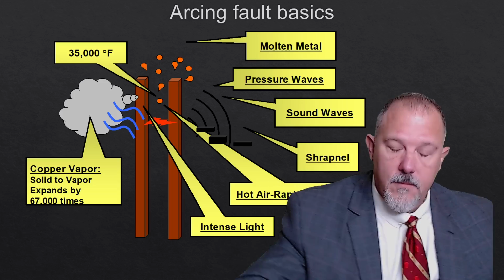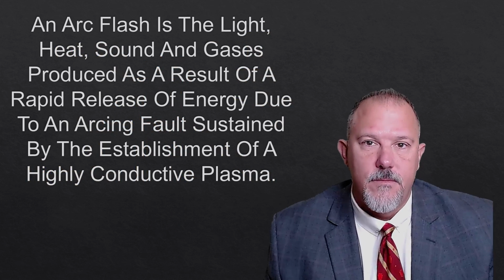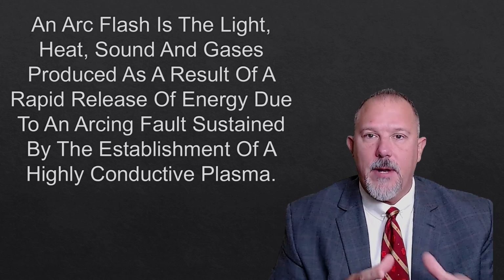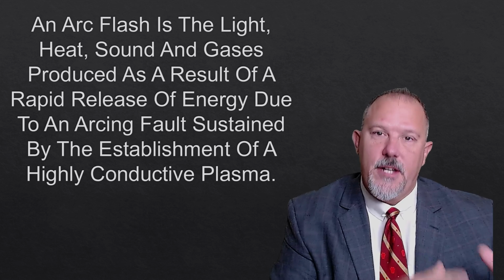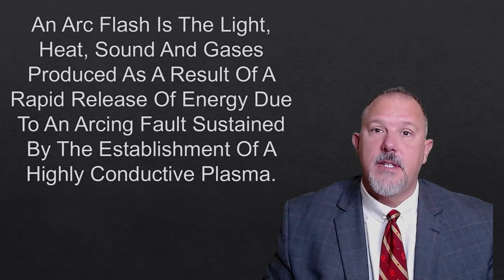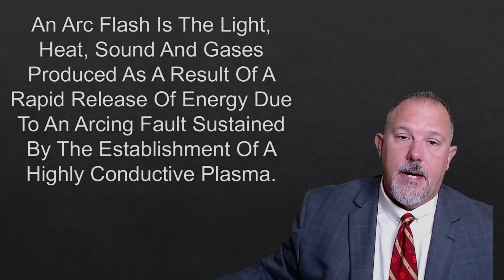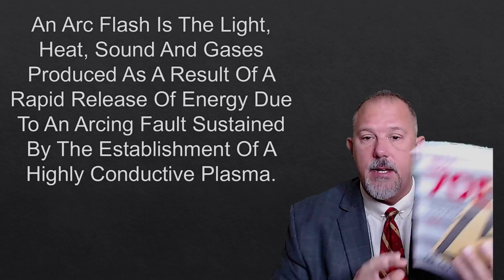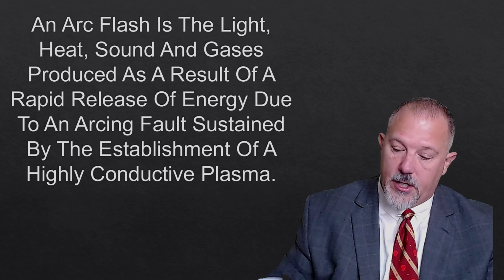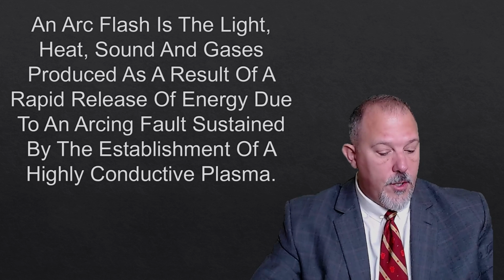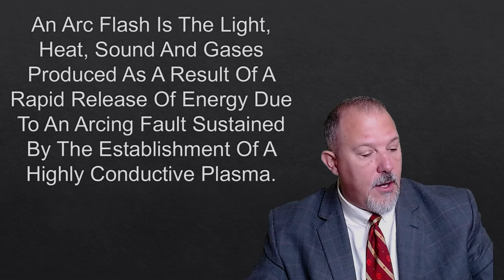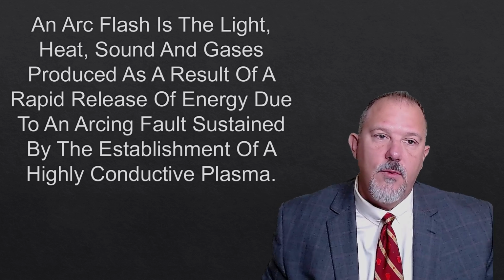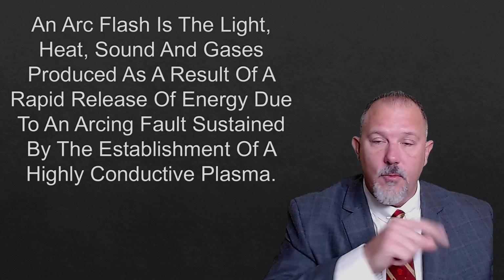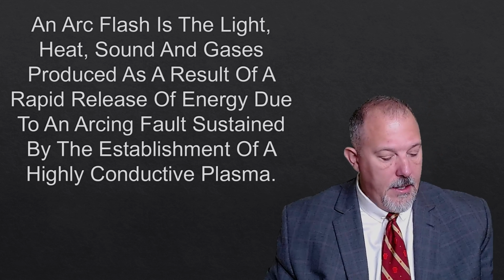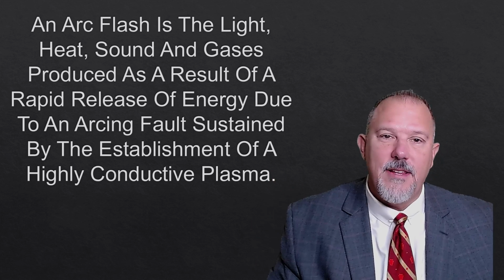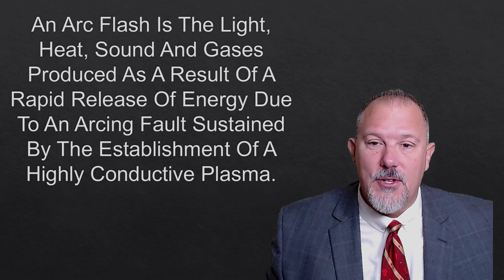So let's talk a little bit about what an arc flash is. And remember, I told you earlier, there is no real definition for the term arc flash in any of the standards. 70E doesn't include one. Now, if I look at 70E, and I'm using the 2021 version, if we go to Article 100, what you'll find is a definition for the arc flash hazard, but it doesn't tell you what an arc flash is. I'll read that to you, but I'm going to read this one to you too. When there's not a definition of the term arc flash, what do you do? You make one up. So I made this one up.